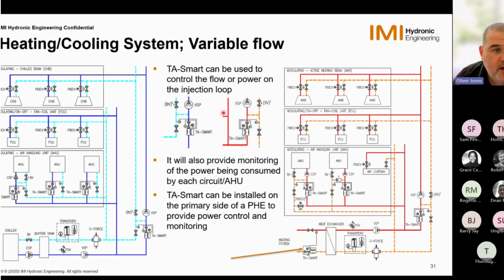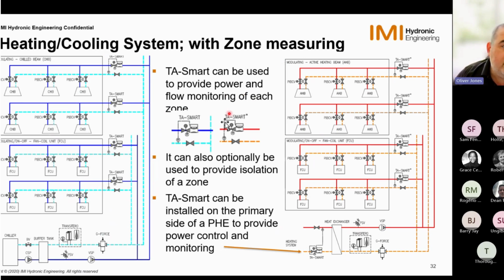For heating and cooling systems on variable flow, again, it can be used to control the flow or power on the injection loop itself. It'll also provide the monitoring of the power being consumed by each circuit AHU. And the Smart can also be installed again on the primary side of the plate heat exchanger and provide power and control monitoring. So on heating and cooling systems with zone measuring, again, we can use the same valve to provide our flow and power monitoring of each zone. So we've got 4 listed on these units itself. And then again, we can use those as isolation to shut those zones off when these parts of the building are not being worked on or worked in.